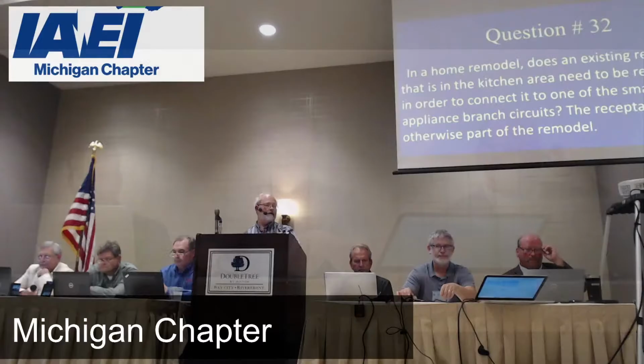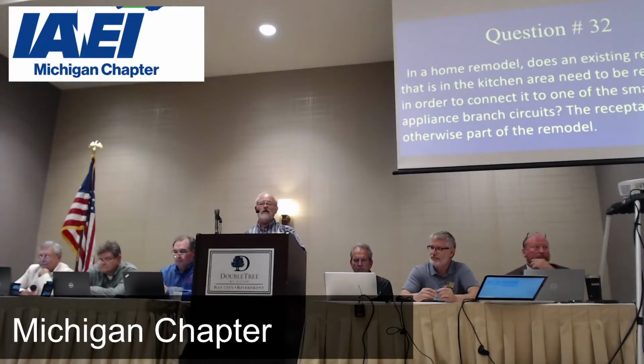It says, additions, alterations, and repairs to any building, structure, or premise shall conform to that of new installation without making the existing building comply with all the requirements of the code. So if that portion's not being affected, you cannot go and make them do anything to that unless they choose to. So my answer to that would be no, you don't have to do anything there. Good with that one?